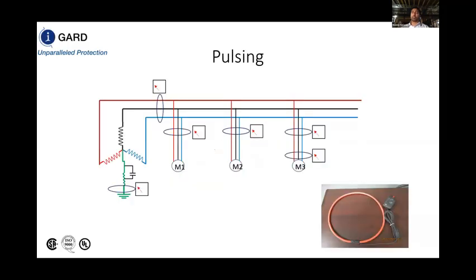With respect to pulsing, this is a method for locating faults in a resistance grounded system, provided that you have process continuity. Let's say, for example, that motor 3 experiences a fault on phase B. Now we've detected that fault at our CT neutral, and we've alerted maintenance that there's a fault in the system. Maintenance knows that there's a fault, but doesn't know where it's coming from. So what they can do is implement the pulsing feature from our touchscreen display.